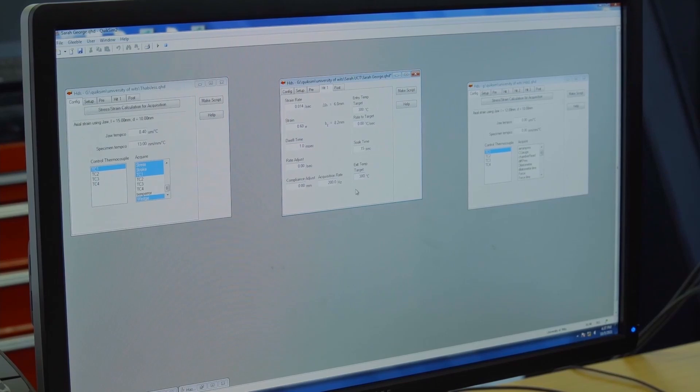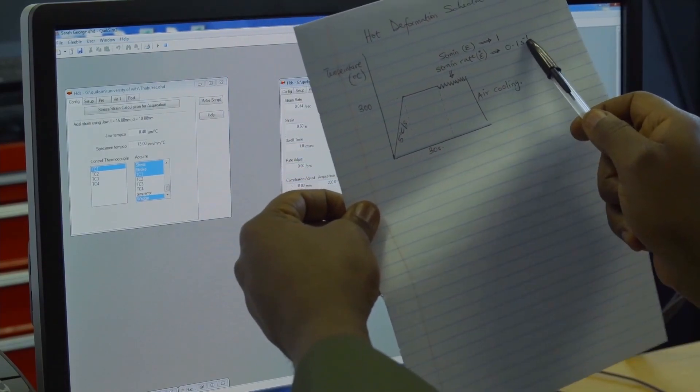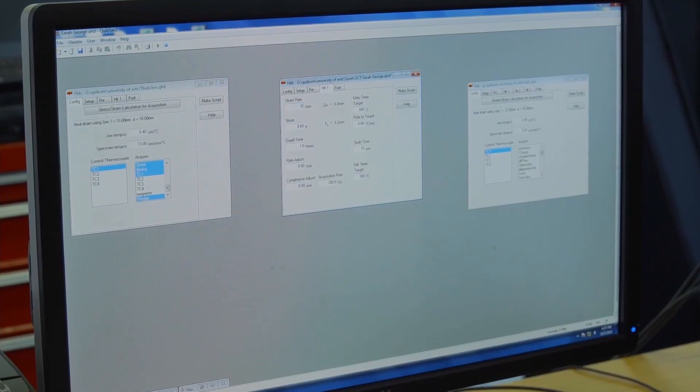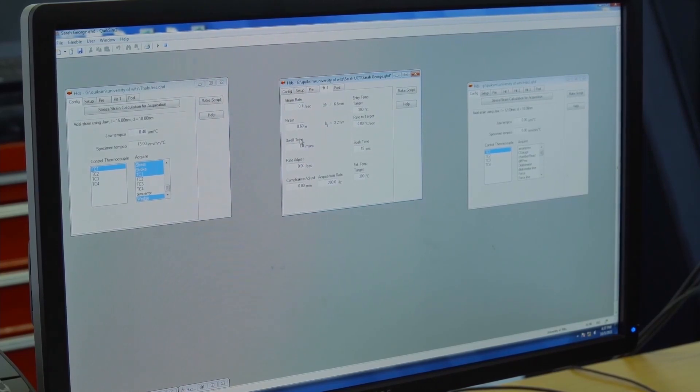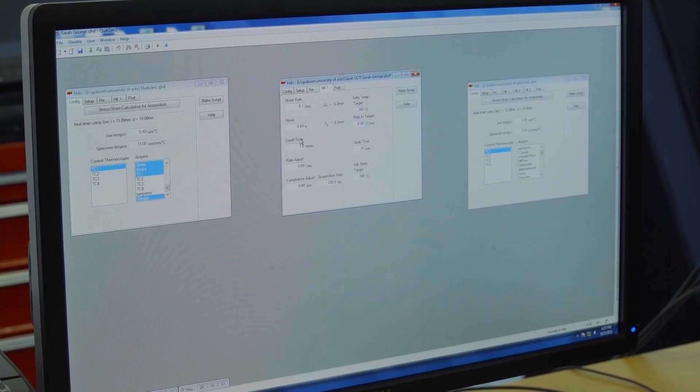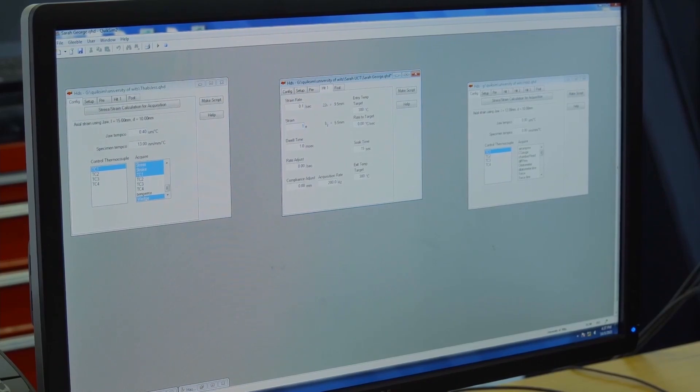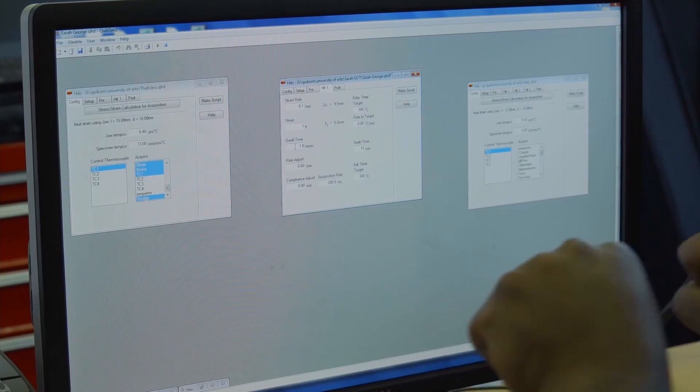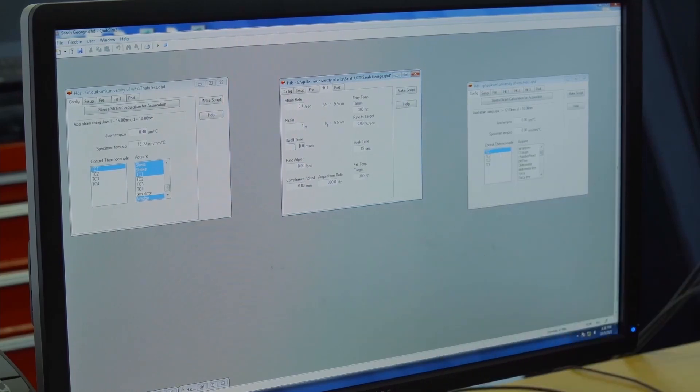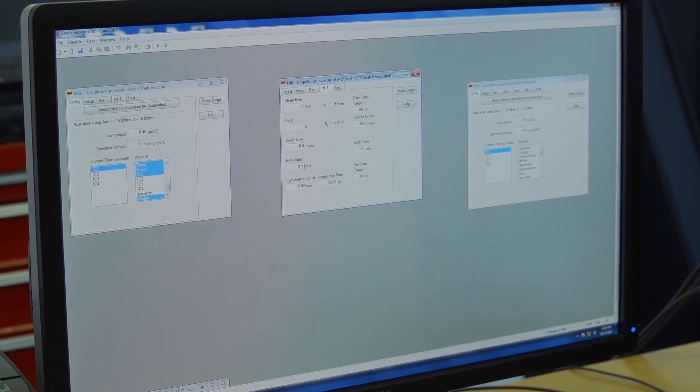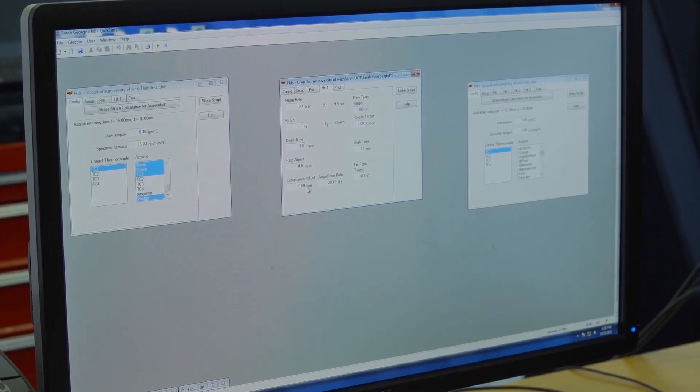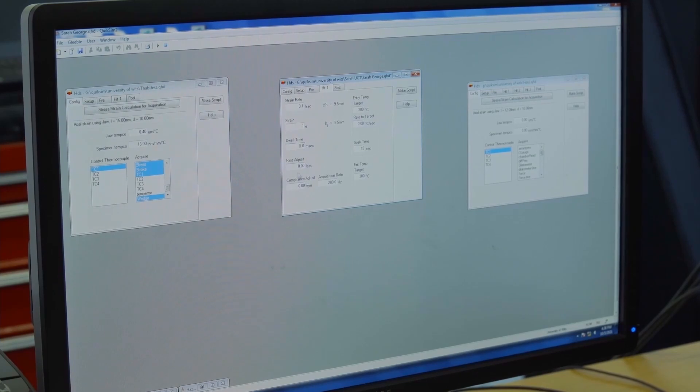We have our rate set at zero degrees Celsius per second because we are not bringing down the temperature. We're going to enter from the pretreatment mode to the deformation mode at the same temperature. I'm going to cool in air anyway. I'm not going to ask the Gleeble to control the cooling for me. We need to set the strain rate. According to the diagram here, it's 0.1 per second. We want to deform to a strain of one. I'm reducing from about 15 mm to 5 mm. The dwell time is the time it will stay on the sample before deformation.